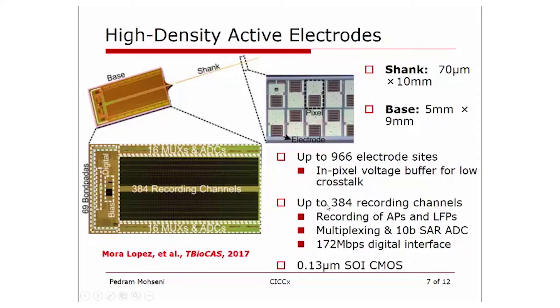Up to 384 recording channels are placed on the back end of the probe in a five-millimeter by nine-millimeter area. All recording channels are reconfigurable for recording both action potentials and local field potentials. Multiplexing in the back end reduces the number of signal lines coming out of the probe, with 10-bit ADC conversion and ultimately a very high data rate of 172 megabits per second interface to transfer all data from the probe to the outside world.